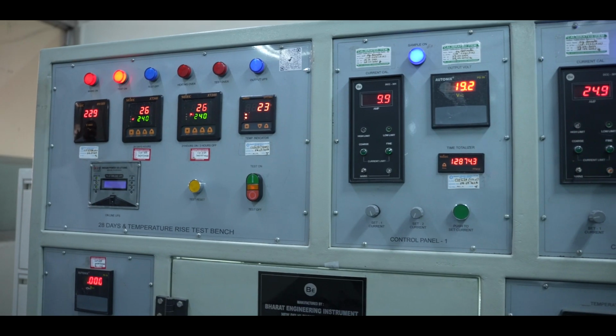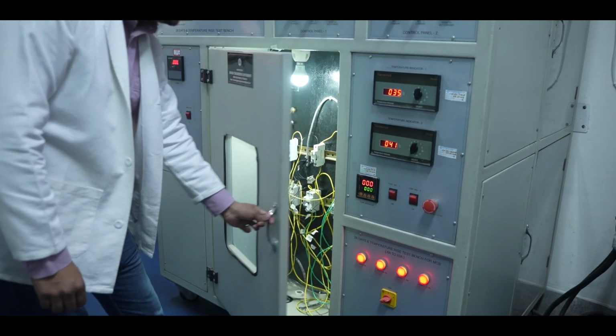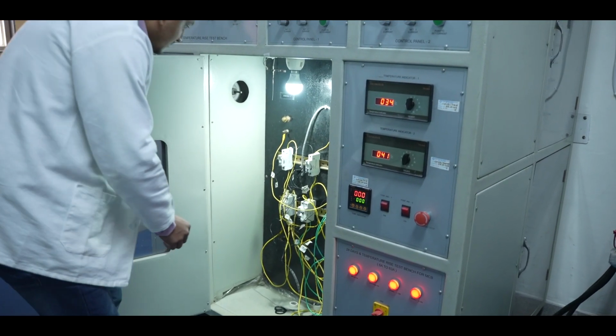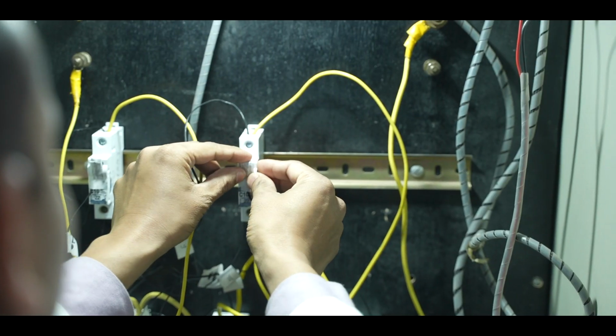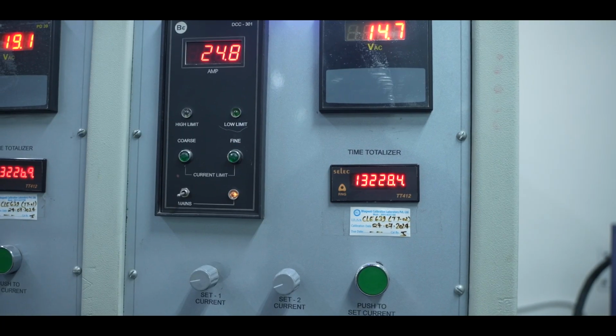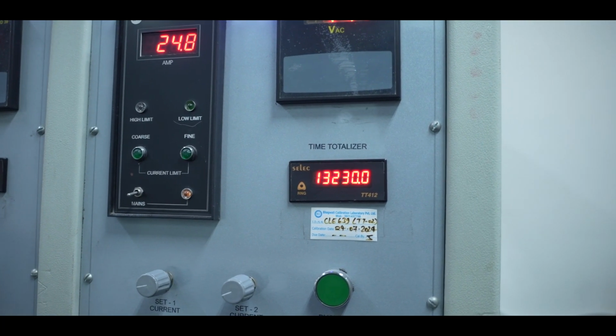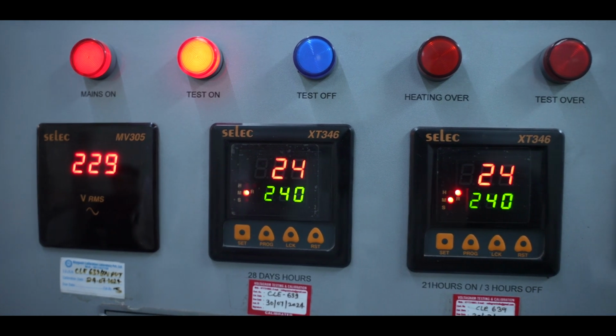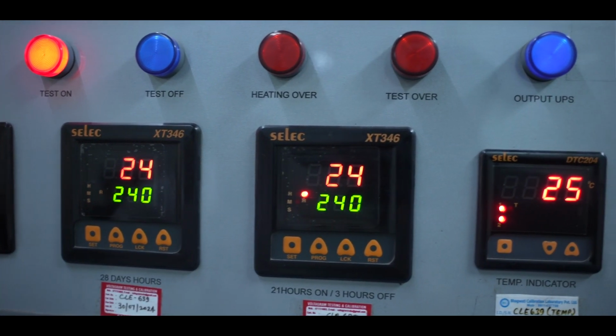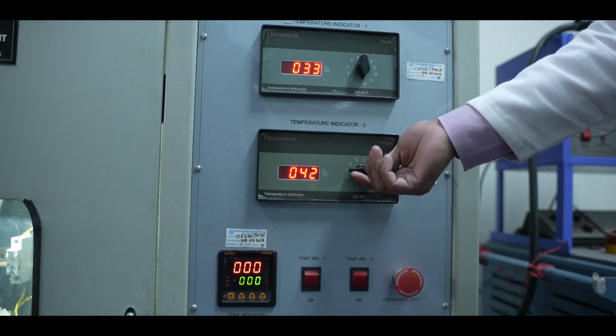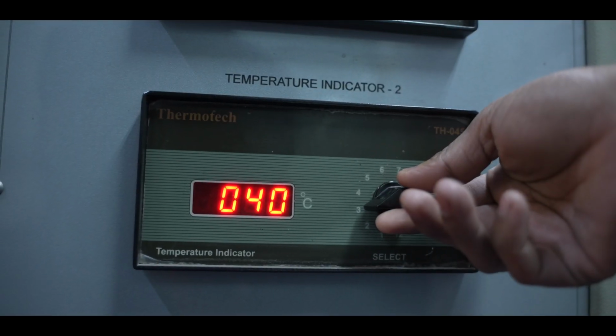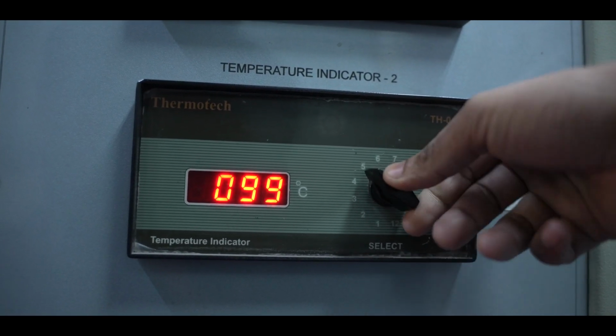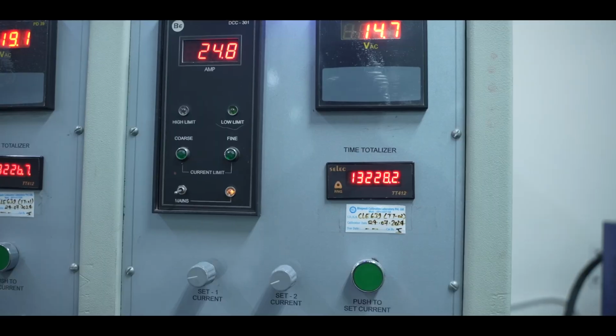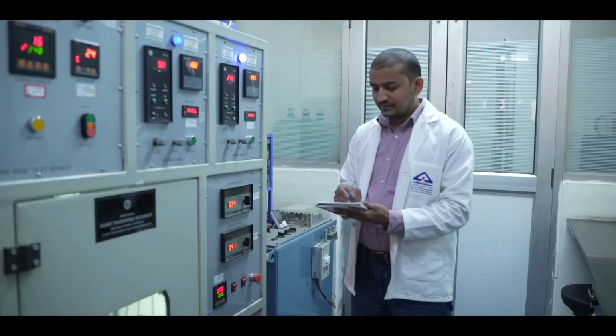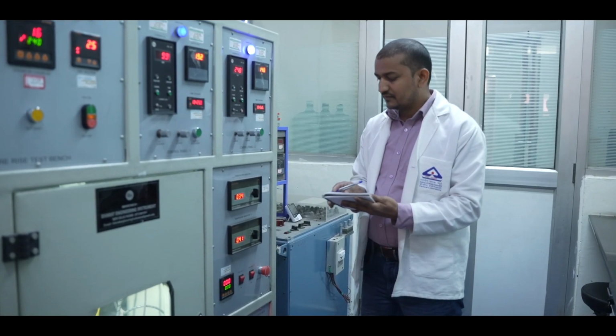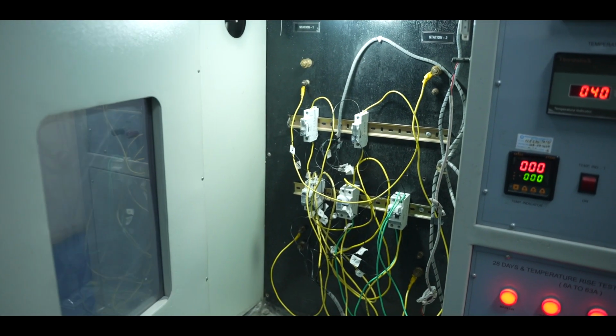Temperature rise test. The temperature rise test ensures that circuit breaker components remain within safe temperature limits during operation. The test is conducted for a duration of 4 hours under normal load conditions. The temperature rises of parts such as external terminals and operating mechanisms are measured and should not exceed specified limits, like 60 degrees Celsius for terminals and 40 degrees Celsius for operating mechanisms. This test verifies that the circuit breaker operates safely without causing damage or overheating surrounding parts.